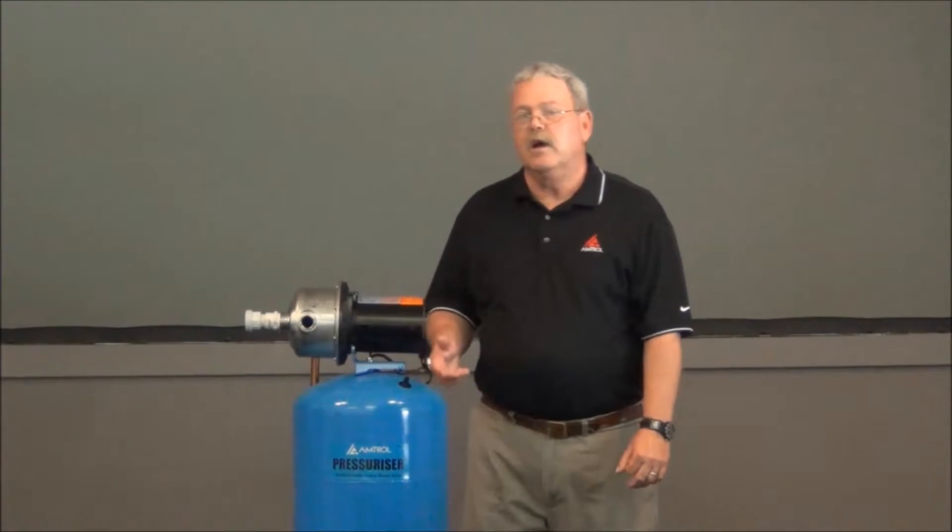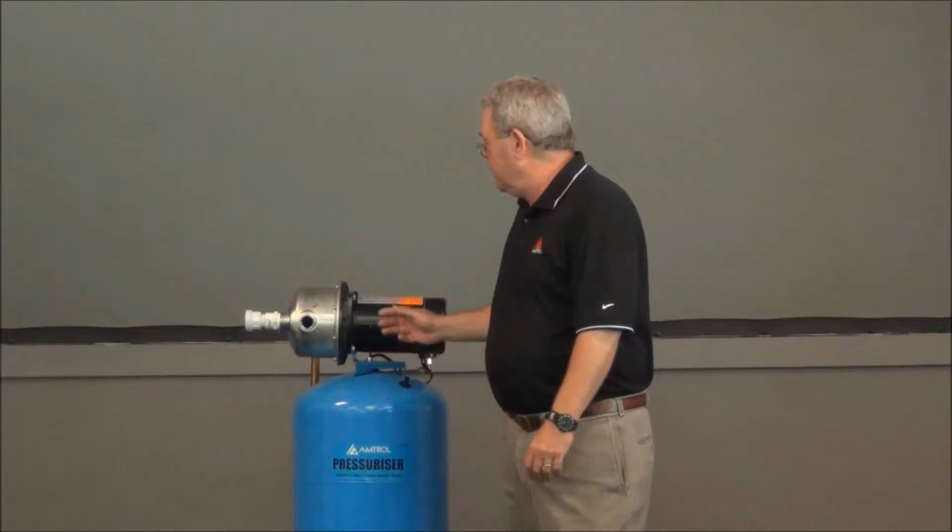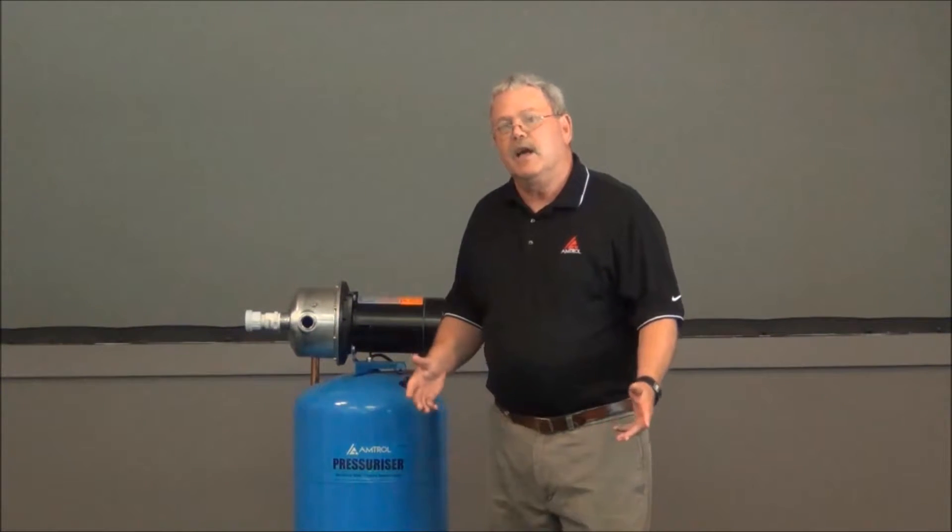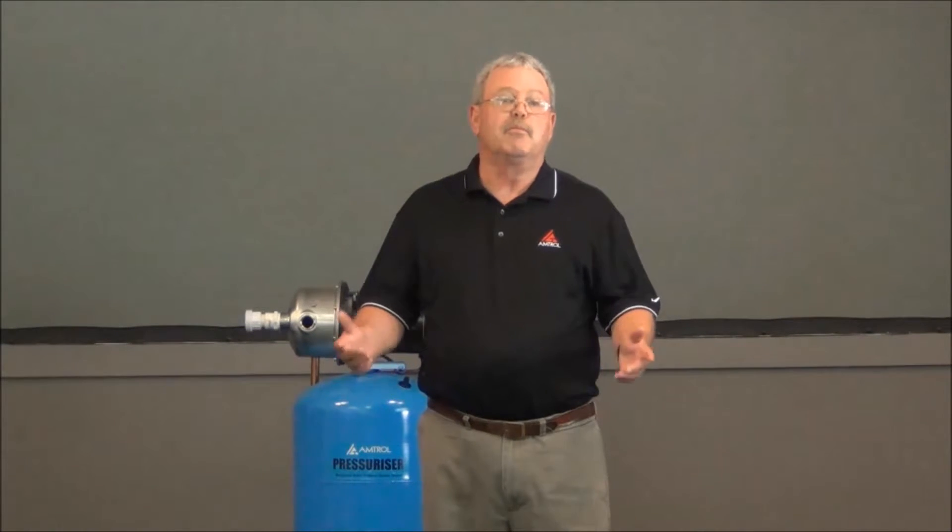One of the other things that we do see is, you know, my pump is overheating. Well, in the summertime when everybody's using their air conditioners and their pumps and watering the grass and so forth, we do run into situations called brownouts sometimes. And when you run into a brownout, that means you've got low voltage.